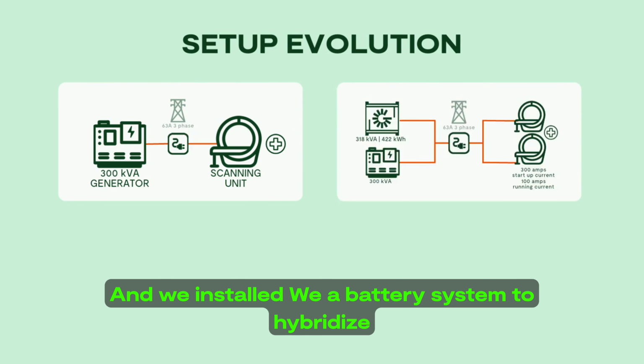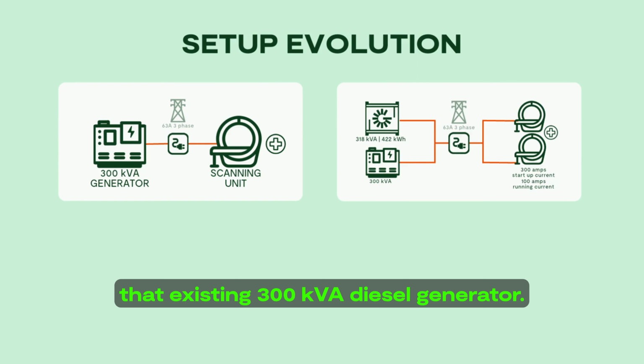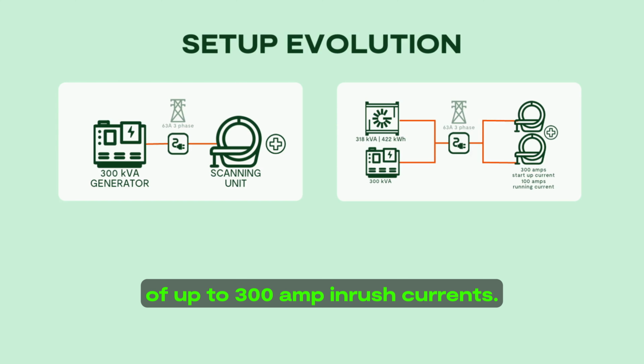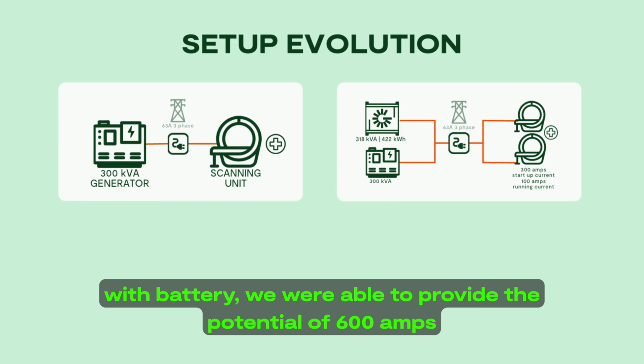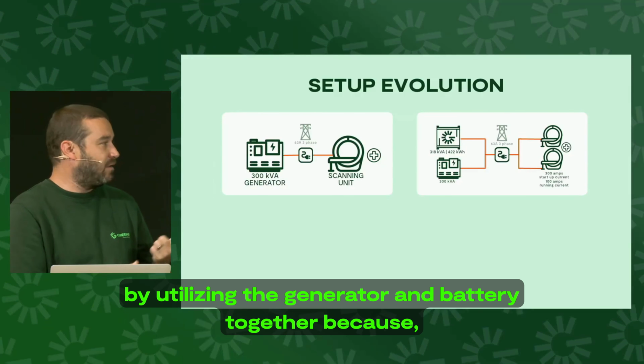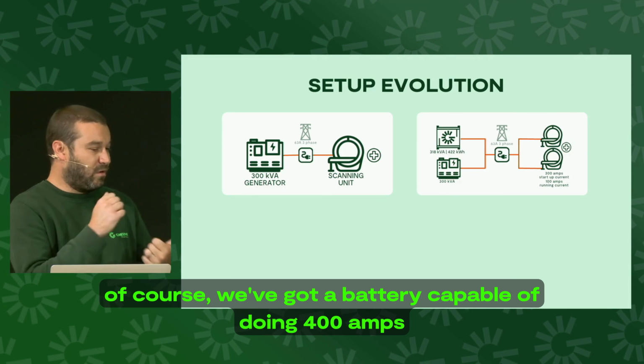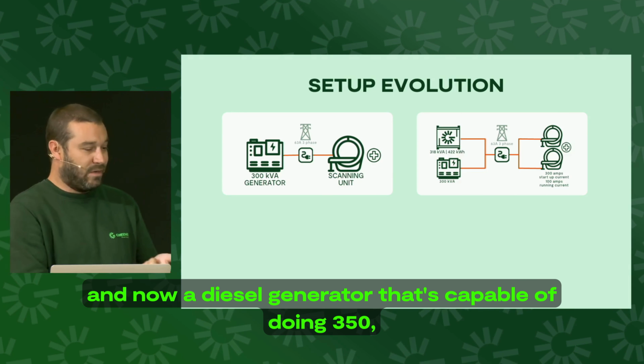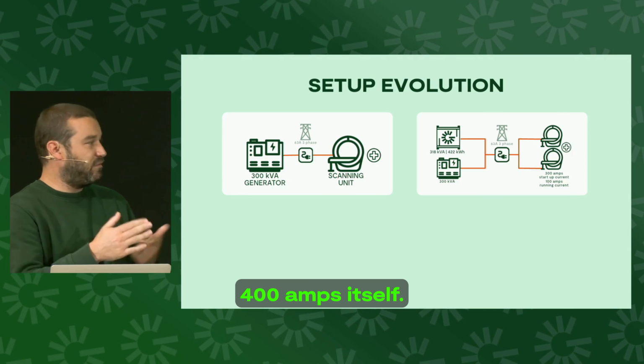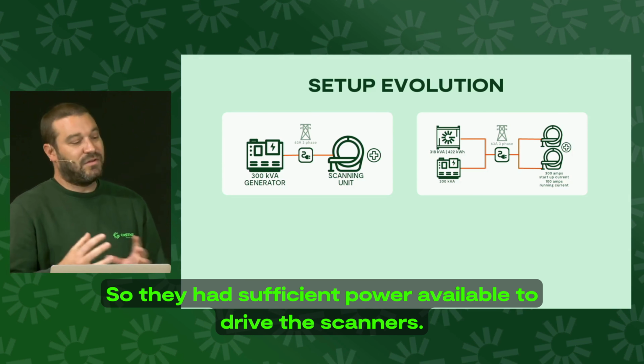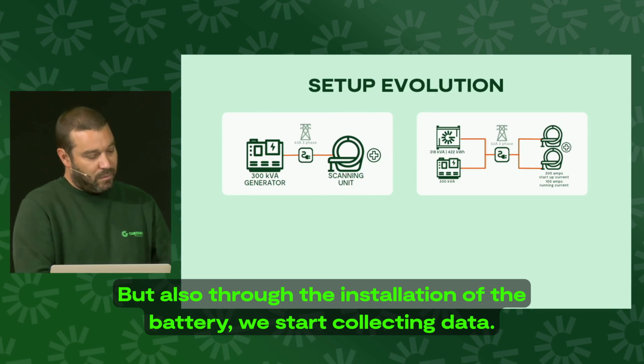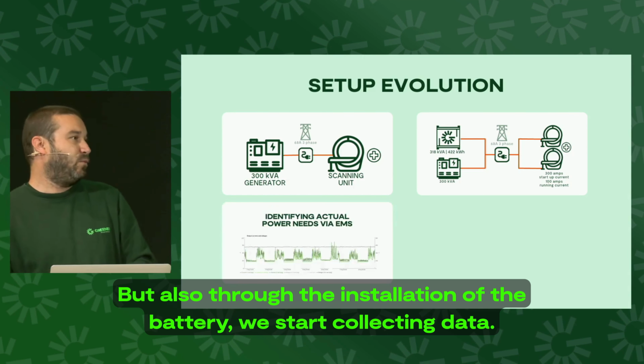So Greener came in and we installed a battery system to hybridize that existing 300 kVA diesel generator. At the same time, a second scanner. So we now had two loads with potentials of up to 300 amp inrush currents. But by hybridizing the generator with the battery, we were able to provide the potential of 600 amps by utilizing the generator and battery together. Because, of course, we've got a battery capable of doing 400 amps and now a diesel generator that's capable of doing 350, 400 amps itself. So they had sufficient power available to drive the scanners.